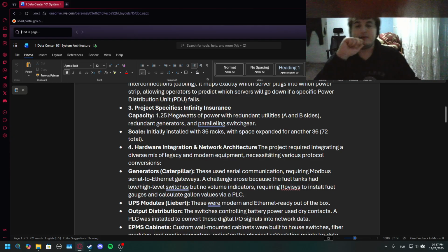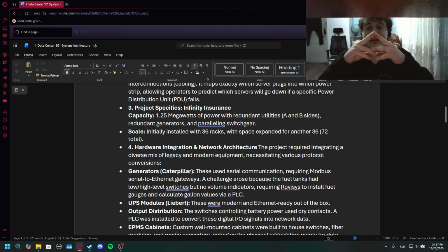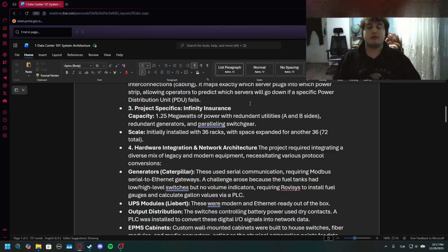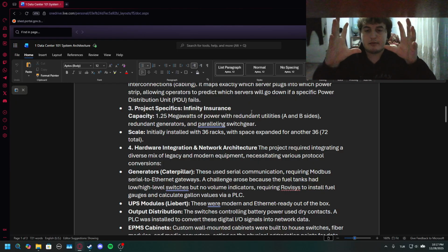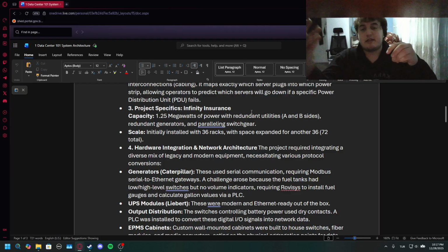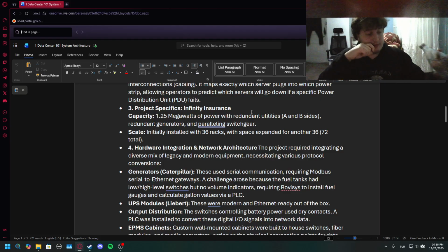Generators: Caterpillar. These use serial communication requiring Modbus serial-to-Ethernet gateways. A challenge arose because the fuel tanks had low and high level switches but no volume indicators, requiring the company to install fuel gauges and calculate gallon values via PLC. So there was a problem with the generators needing an additional piece of technology. The company doing this is the one I'll link in the video. The fuel gauges are basically for calculating gallon values, meaning the generator itself didn't have that initially, so they had to fix that problem.